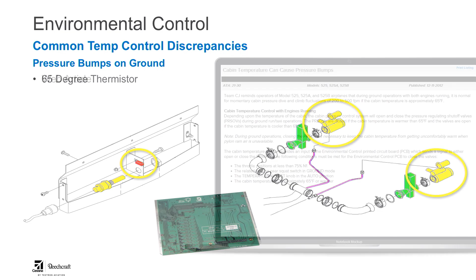So this kind of gives you some information on what to look for. Again, we just want to make sure it's cycling around that 65 degrees. The way to mitigate it is pretty easy. Go to manual temp control and don't touch it. Let it sit for a few minutes. What you're doing is you're bypassing that 65 degree circuit. When it's in manual, it turns on the PRSOVs, and you're going to dump some warm air in there. Let it warm the cabin up to 70 degrees or so, and then go back to auto. And then at that point, it's not hovering around 65. It's not going to cycle on and off like it was, and you can go on your way.